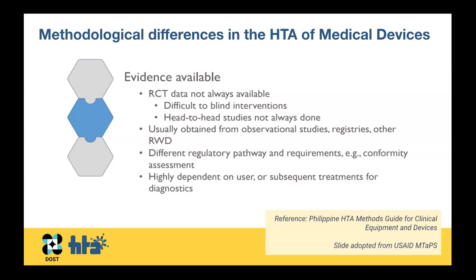It has a different regulatory pathway and requirements. So for drugs, it's usually certificate of product registration, but for equipment for the Philippines, the FDA would have what you call the certificate of medical device registration and the certificate of medical device notification, depending on the risk of the equipment. So if it's a high risk equipment, then it would require a CMDR or a higher risk level. If it's low risk, then it can be downgrade, or rather, I don't want to say downgrade. Then it would have to go through the CMDN for lower risk devices. So again, market dynamics is very, very different.